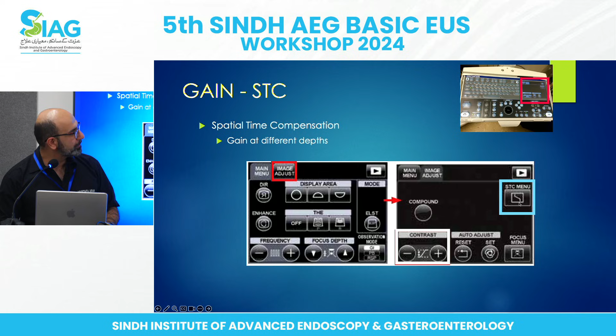And then within there, you actually have this STC menu too, so you can now do fine-tune adjustment of your image. You do the main gain, it's the bigger focus, and then the fine focusing you can use STC for. And this is how gain can affect your image. So if it's too bright, too high a gain, you lower the gain. If the clarity is not as much, then you can increase your frequency, and then you can adjust your STC setting to get the optimal image.